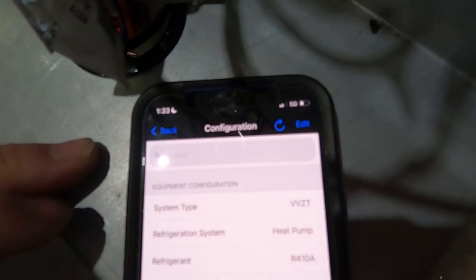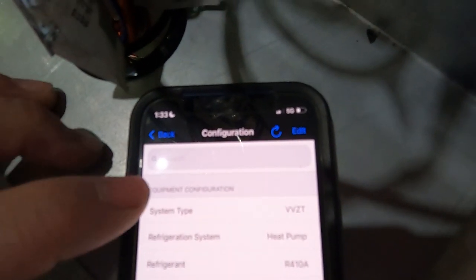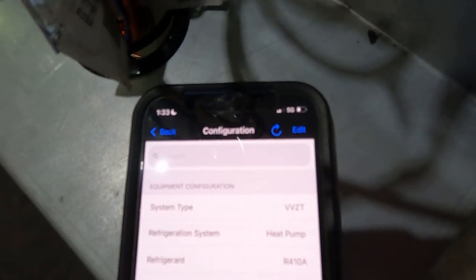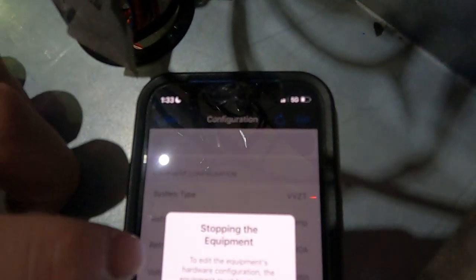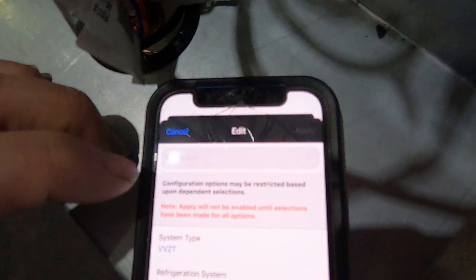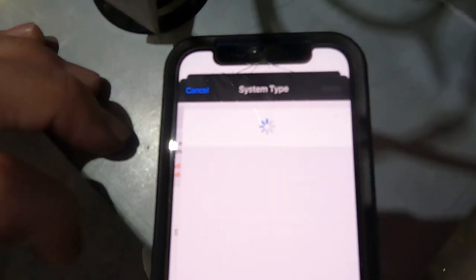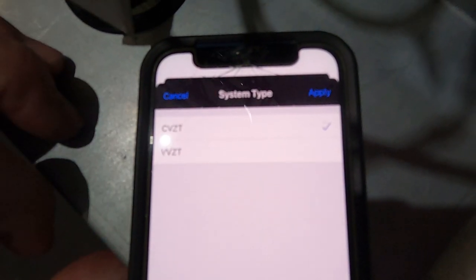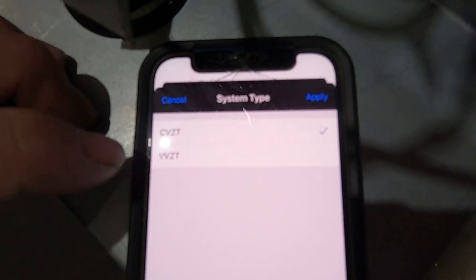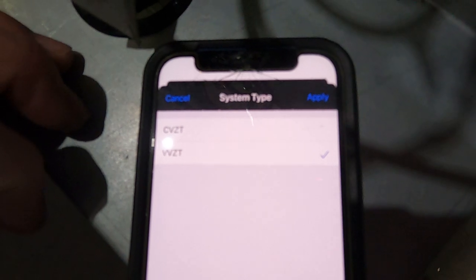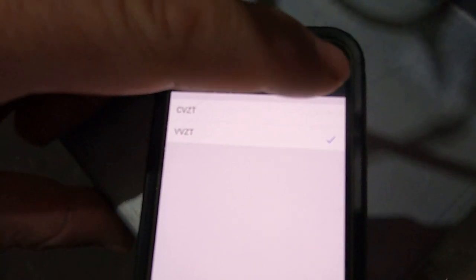Again, what I'm seeing coming from the factory is that it's programmed for constant volume and it will look like this right here coming from the factory. You need to change it to the variable volume for the VFD.